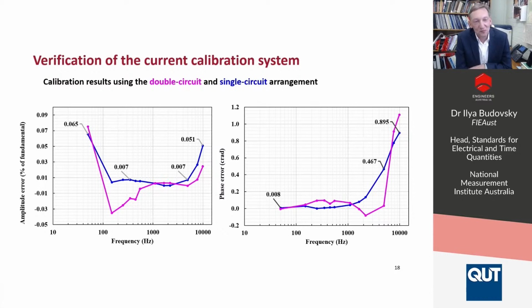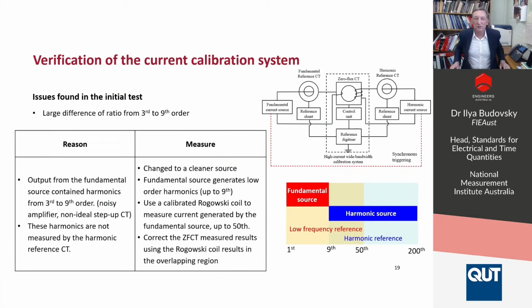Well, if you see 1.1%, then probably it's okay. But we wanted to understand where some small disagreement has arisen between the two measurements, and you can see the phase, the in phase, and the quadrature component. And I'm glad to report that we found the problem. The problem was that the 50 hertz signal was not pure, so it did contain harmonics that could not be measured by the reference CT, obviously.